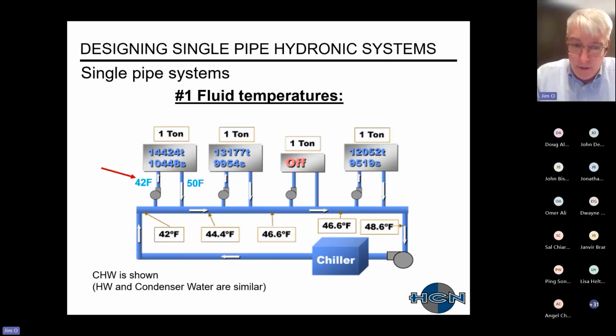You have a chiller providing cooling for it. So your chiller is producing 42-degree water. On the left, that 42-degree water enters the first unit. It then comes out at 50 degrees. That 50 degrees then mixes with the 42-degree water, and the water temperature rises a little bit. As you can see in this example here, it went from 42 to 44. So now the second fan coil receives 44.4-degree water entering it, comes out a little bit warmer, warms up, etc.